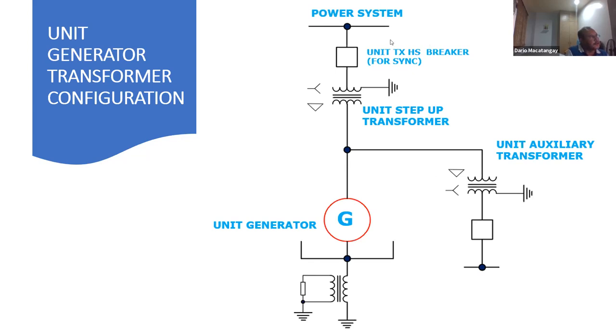So you can see there's a breaker here, okay, on the top. So when you are doing maintenance on their system, typically you would open this breaker, secure this breaker open, and then you can maintain the generator.